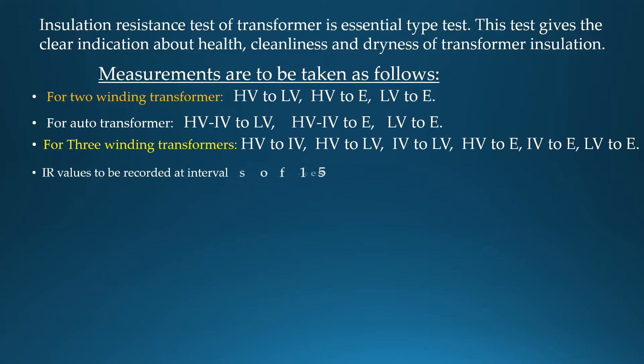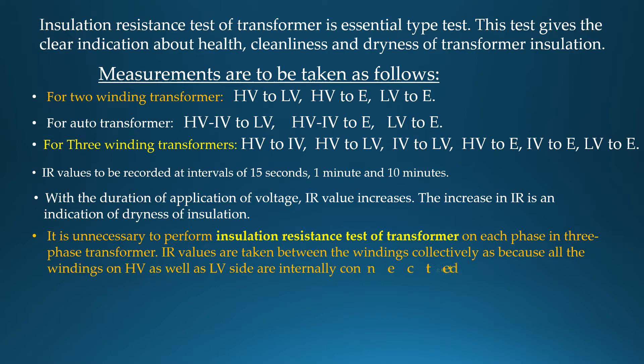IR values are to be recorded at intervals of 15 seconds, 1 minute, and 10 minutes. With duration of application of voltage, IR value increases. The increase in IR is an indication of dryness of insulation. It is unnecessary to perform insulation resistance test on each phase in a three-phase transformer, as IR values are taken between the windings collectively, since all windings on HV as well as LV side are internally connected together to form either star or delta.